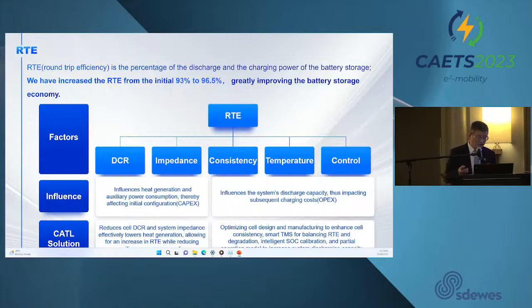RTE, round-trip efficiency, is the ratio of discharged energy to charged energy. By reducing cell resistance (DCR) and system impedance, and by implementing new technologies such as intelligent state-of-charge calibration, we have increased the RTE from an initial 93% to currently 96.5%, greatly improving the competitiveness of lithium-ion batteries for stationary storage.